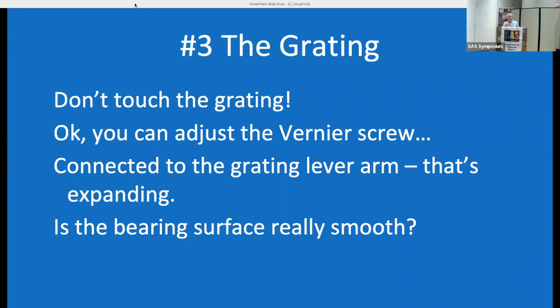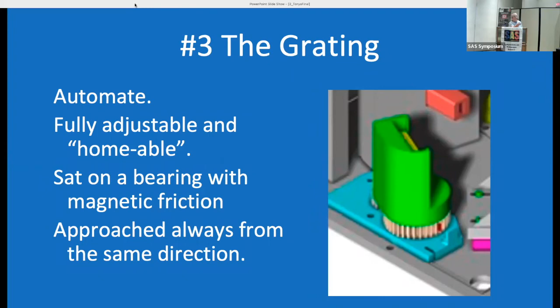Jerry's design. Automated the wavelength selection. Up. Down here is a bearing. Underneath is two pairs of neodymium magnets. I think I've got a picture of this somewhere. There you go. So this is the grating holder turned upside down. That's where the bearing fits. Two pairs of neodymium magnets acting on a washer underneath the bearing. It grips the washer and it provides drag.